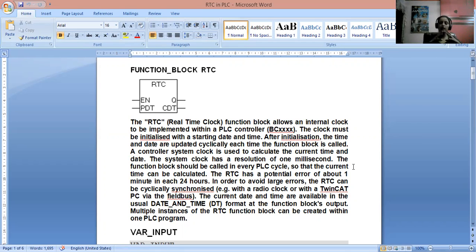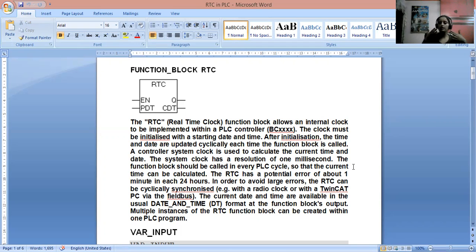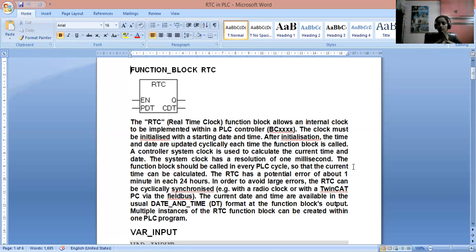Each time the function block is called, the PLC controller's system clock — which is based on RTC — is used to calculate time and date. The resolution of the system, which is how quickly it tracks time, is one millisecond. So if there is a difference, it changes within one millisecond. The functional block must be called every PLC cycle so that the current date and time is accurately calculated.